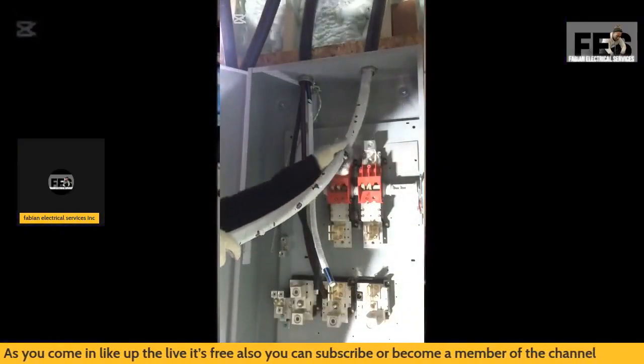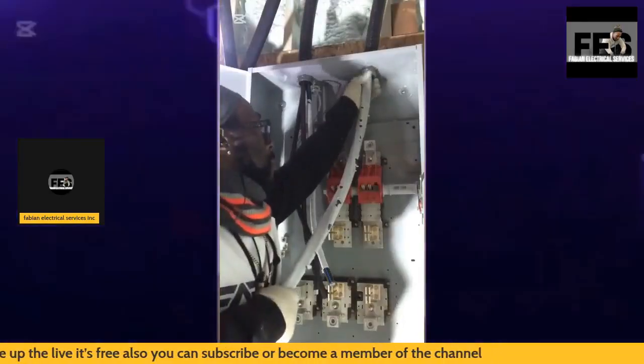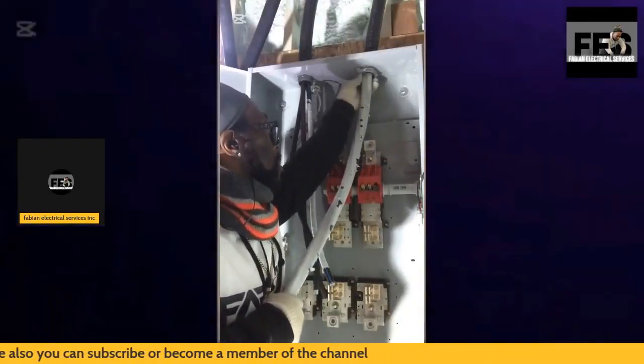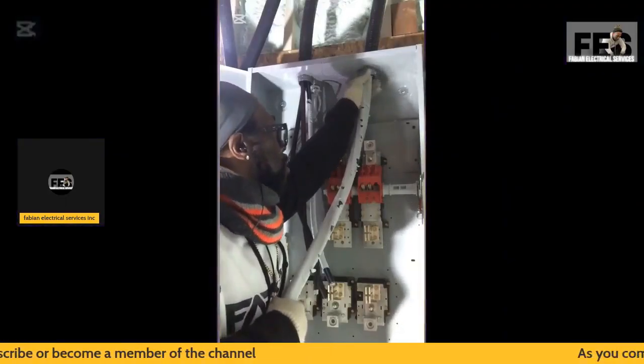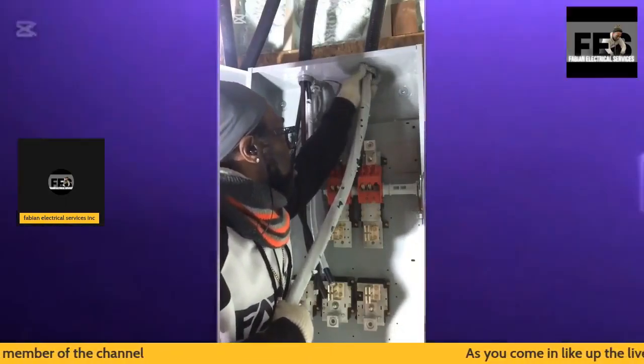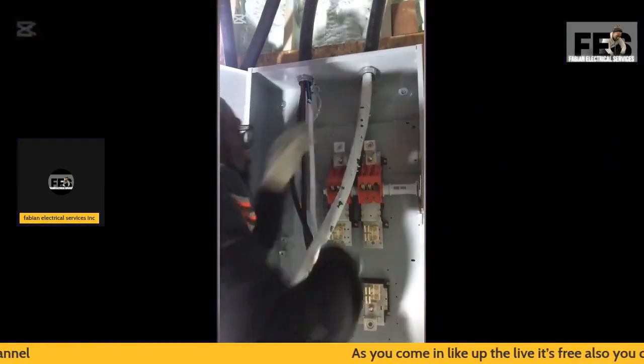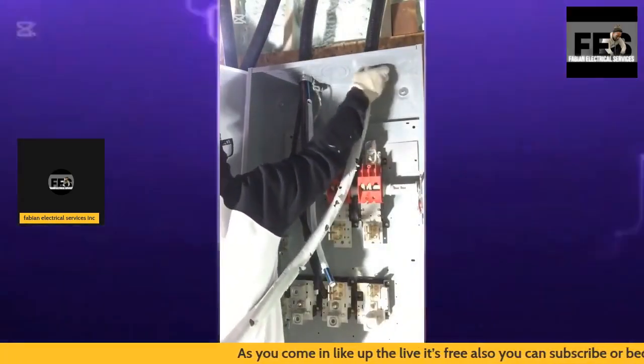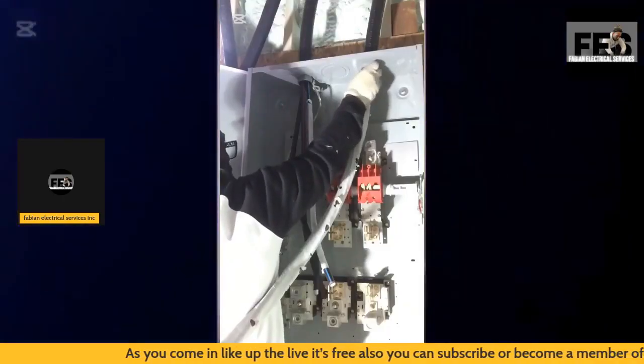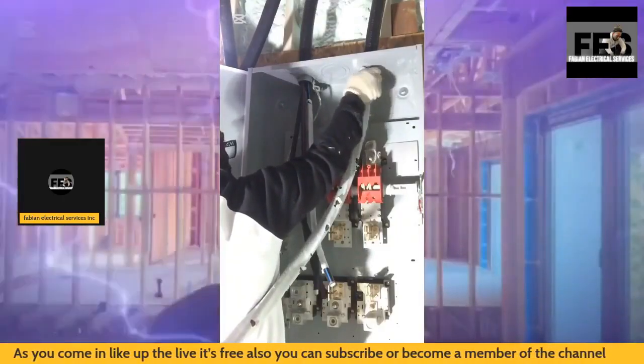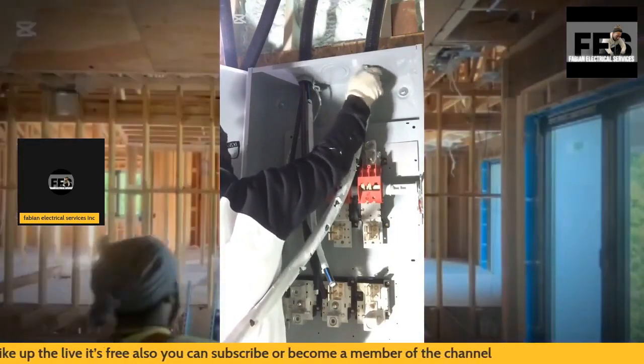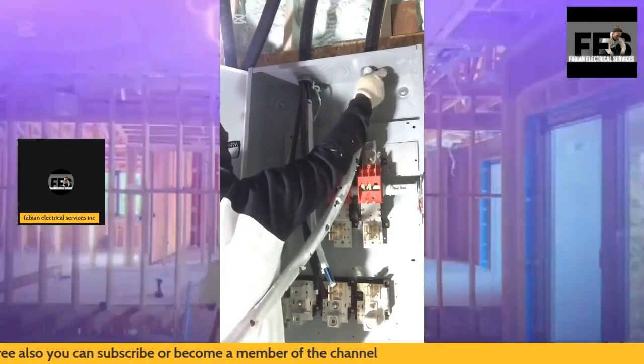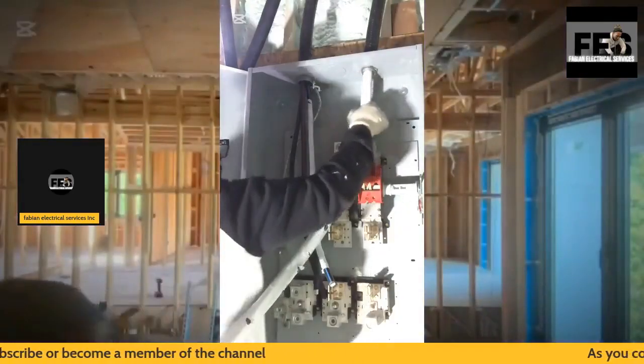I also make sure to put my ground bushing on first. This installation is going to come with the ground bushing connection. The reason is the ground wire has to be grounded off to the actual ground clamp. The ground connection has to be grounded off.